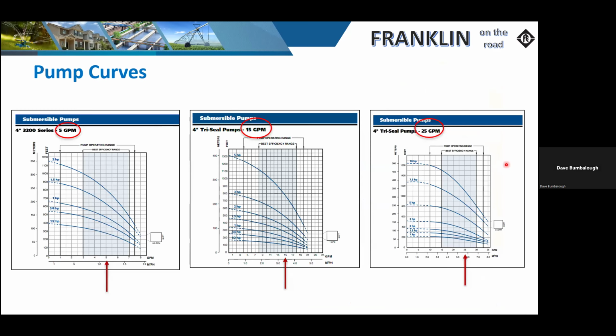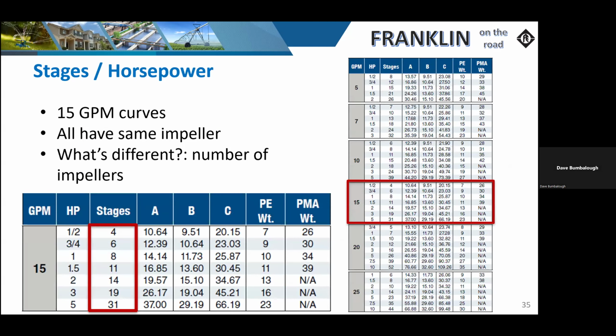And as I pointed out, a 5 gallon per minute is not going to work. Its highest level it can ever pump is about 7.5 before you start damaging the pump. The 15 is ultimately where I need to be. The 25, I can still do pretty good, but it's going to be down here in the lower section of the efficiency curve. So I want to keep an eye on that, and the reason I bring this up is sometimes our suppliers just don't have the product on the shelf. We're in a pinch. We need to get this up and running. So it does pique our attention to look at other alternatives.